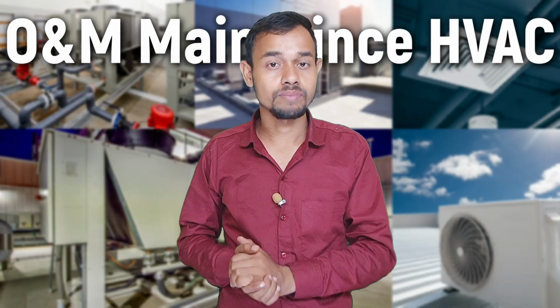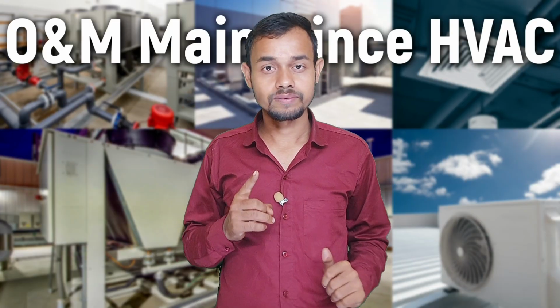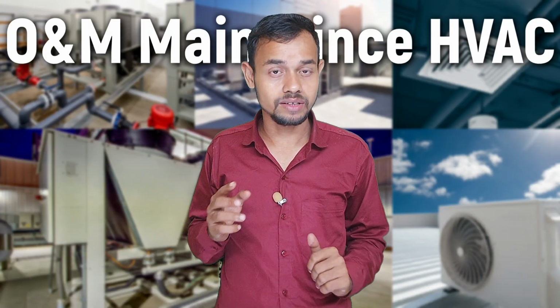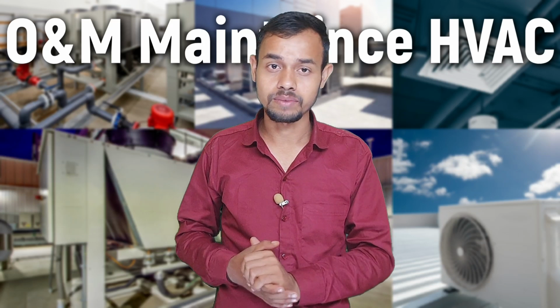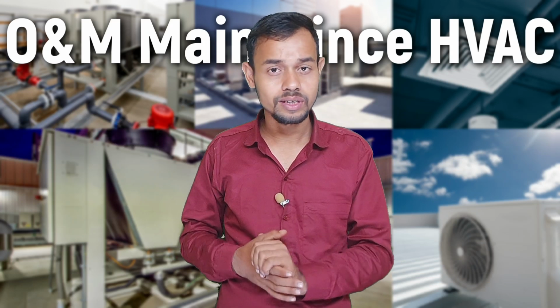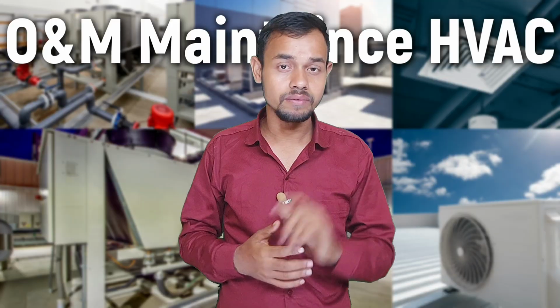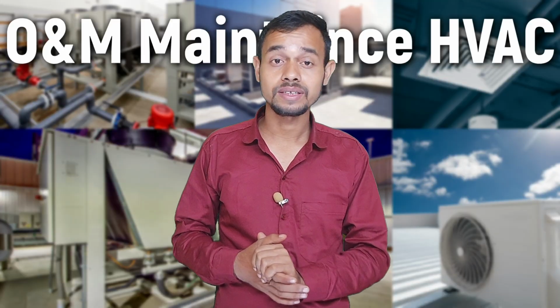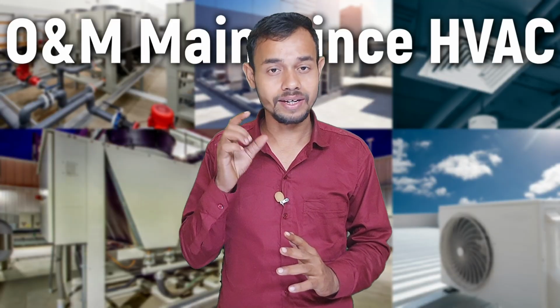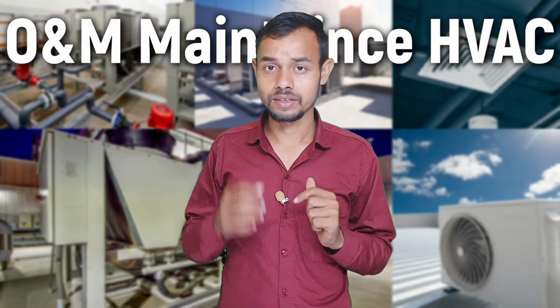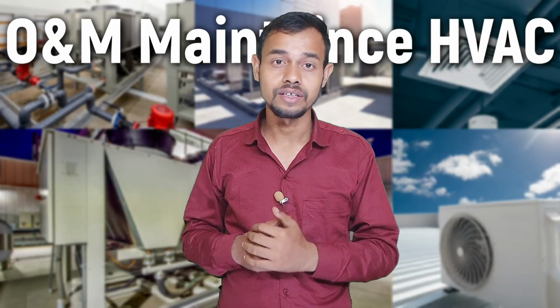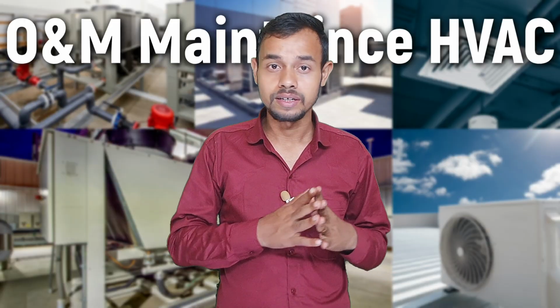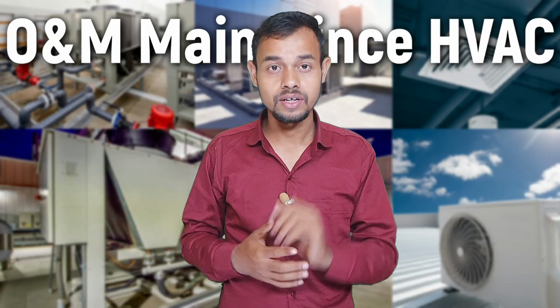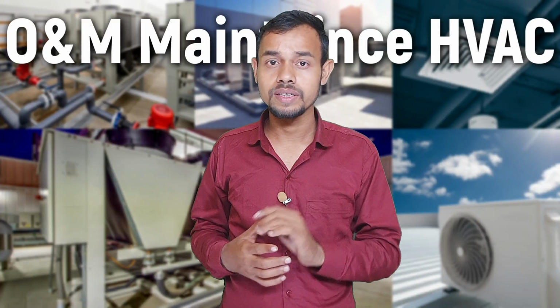So what does the HVAC operator actually do, friends? First is monitoring the chiller plant: chilled water supply and return temperature, condenser water temperature, compressor load, refrigerant pressure, and chiller efficiency in kilowatt per TR. Friends, imagine if the chilled water temperature rises suddenly, cooling across the entire building disappears within minutes. That's why the operator keeps real-time eyes on the plant.